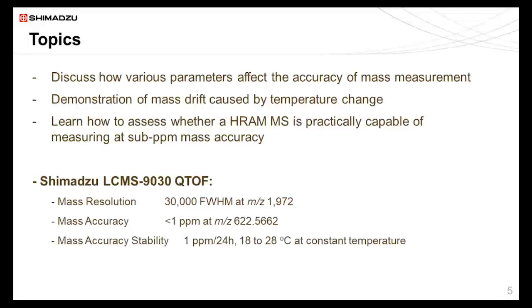Here's a quick recap of Shimadzu's LCMS-9030 Q-TOF. According to the specification, the mass resolution is 30,000 FWHM at m/z 1972, and mass accuracy is better than 1 ppm at m/z 622. Mass accuracy stability, which is our unique specification, is that we sustain 1 ppm mass drift over 24 hours at a constant temperature between 18 and 28 degrees C.